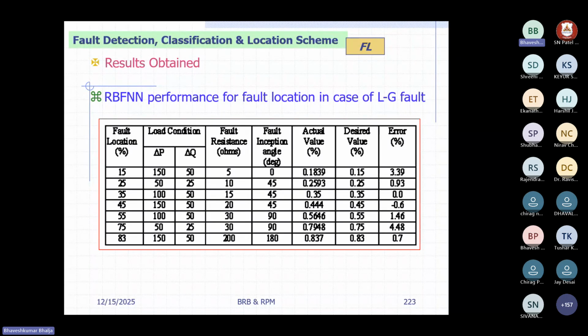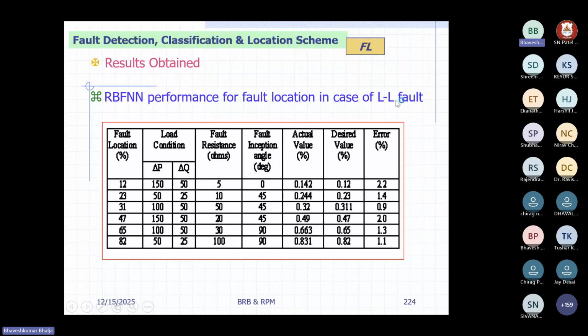And then the load condition, I have changed the active and reactive power flow. I have changed the fault resistance. I have also changed the fault inception angle, and then the actual and desired value of fault location is also there. The last column indicates the percentage error. You can see that the percentage error remains below 5%, right? It is plus or minus 5%. And if you take the absolute value, then this comes on the positive side. So this is how you can have the location part.